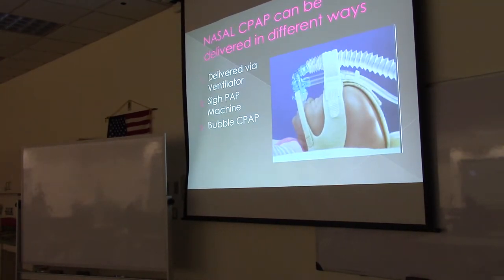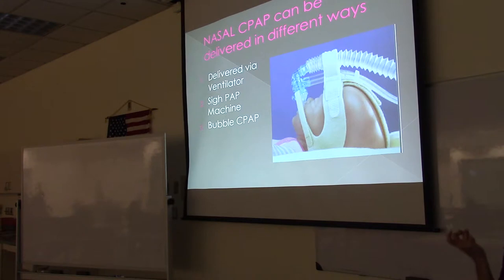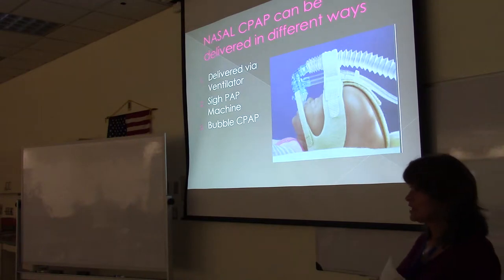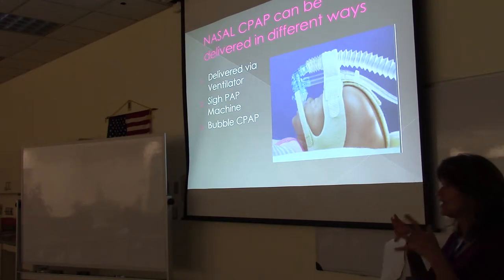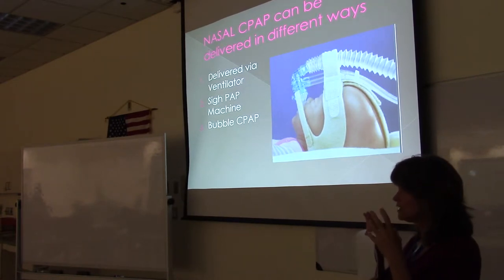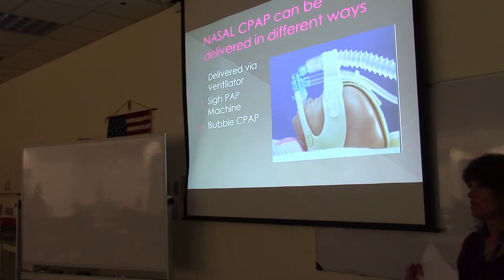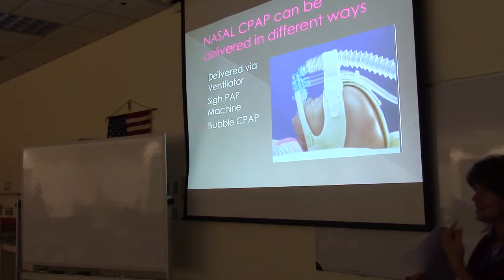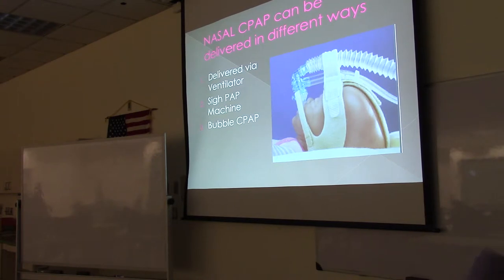There are different ways of delivering nasal CPAP. As demonstrated with Vapotherm, the nasal cannula only occupies about 50% of the opening of the nares. With nasal CPAP, we want the prongs to fit comfortably but to occlude the nares so that a positive pressure can be generated. That's the difference between high-flow nasal cannula and nasal CPAP — with CPAP, the prongs fit snugly in the nares to create positive pressure.